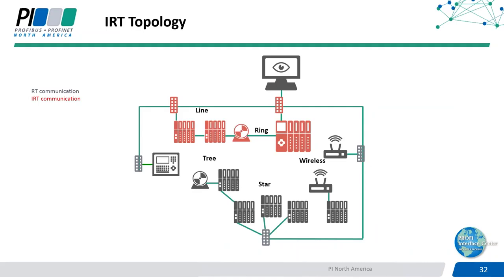For motion applications, it's necessary to have all of your conformance class C devices, those IRT nodes, interconnected on the same domain and network section, because that section of the network is going to be truly deterministic and clock synchronized, so the real-time clock needs to be able to pass between all of those nodes. Other RT or Ethernet nodes can also be connected on edges of that domain, but you can't have an RT node in the middle of that domain, or something like a best-effort switch, because then it wouldn't be able to transfer the clock information.